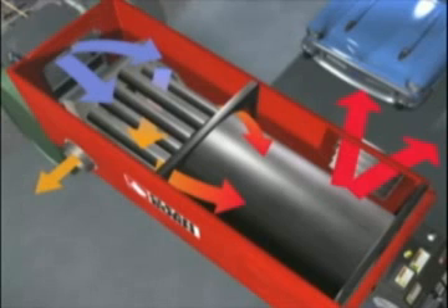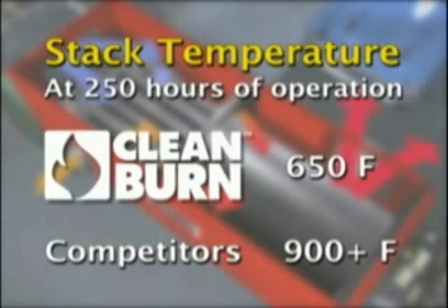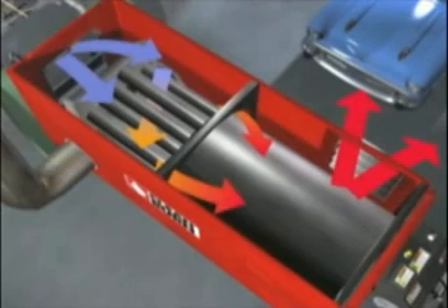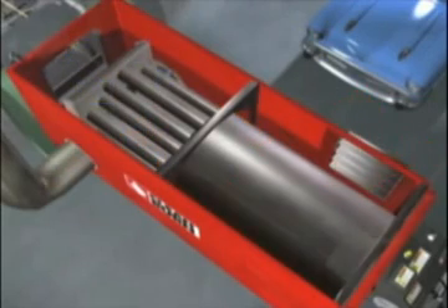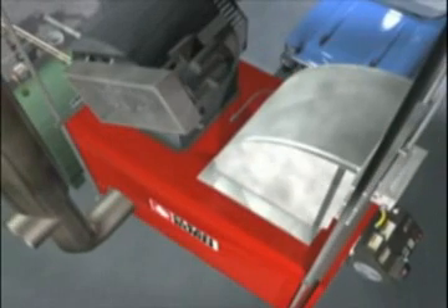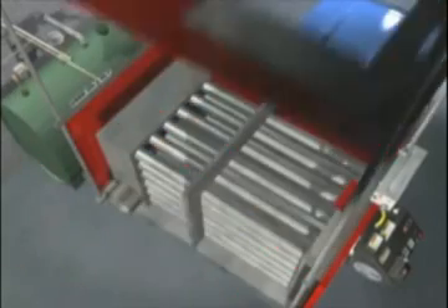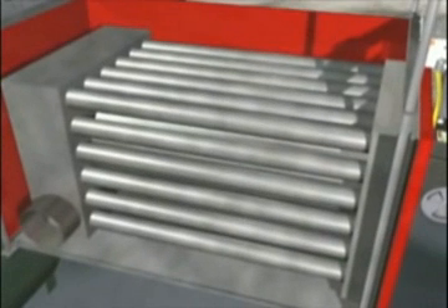nearby wall. Because heat has been efficiently extracted before reaching this point, a CleanBurn stack temperature is significantly lower than that of its competitors. At 250 hours of operation, it is around 650 degrees Fahrenheit, while the competitors measure 900 degrees Fahrenheit or more. CleanBurn is able to take heat extraction to yet another level inside its larger furnaces. It employs an advanced multi-pass approach in extracting heat from the gases produced by the burner, and another multi-pass method in transferring that heat to your shop environment.